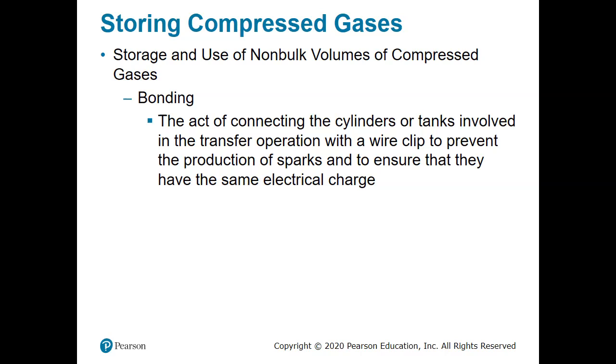And again, usually we see grounding and bonding done together. So we bond together all of the cylinders using just wires, wire clips. And then the last one gets connected to the earth ground so that all that electrical energy just gets dumped into a safe location.